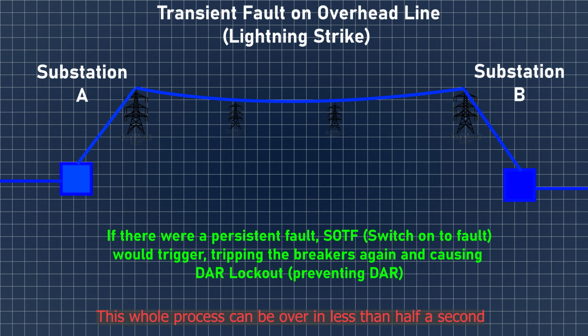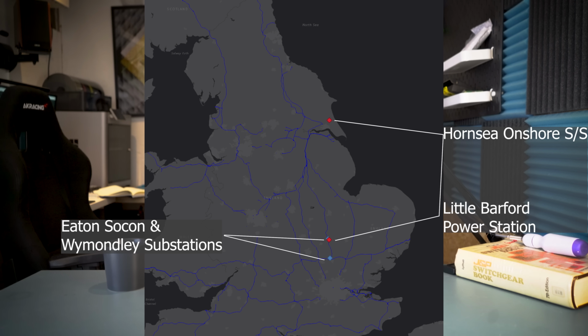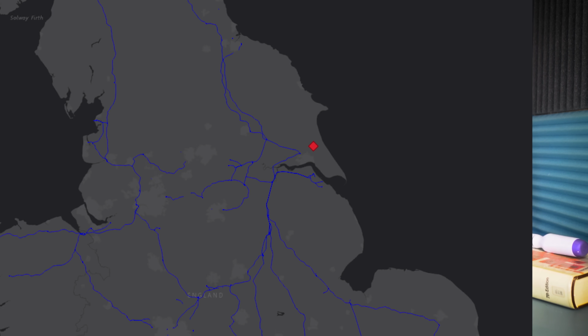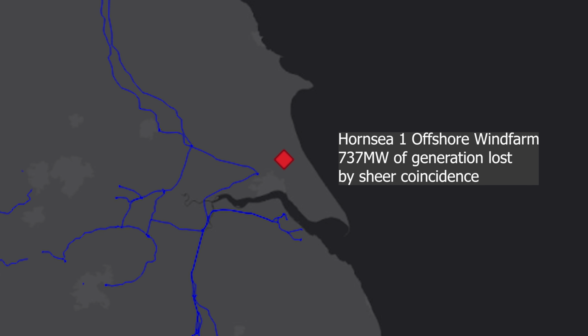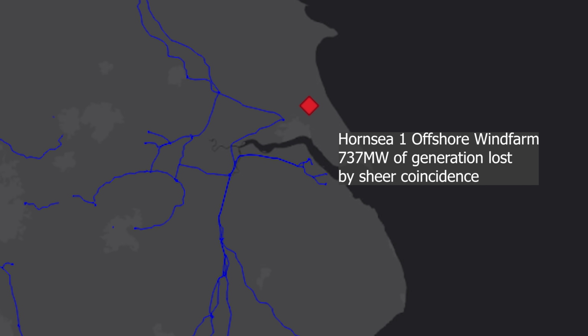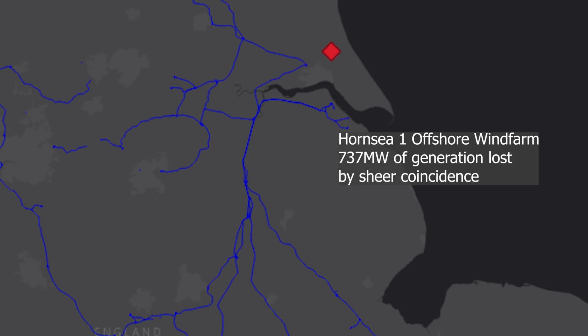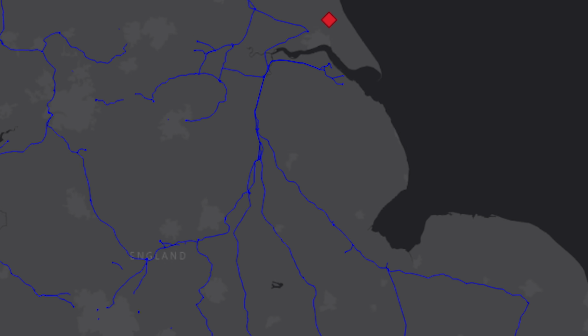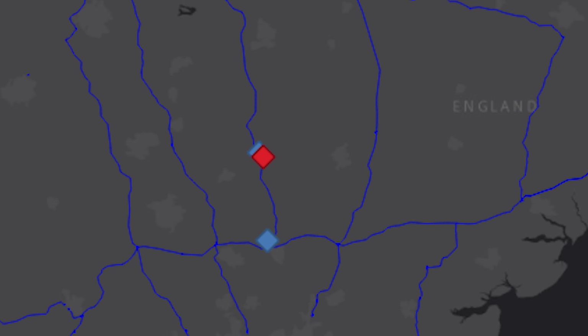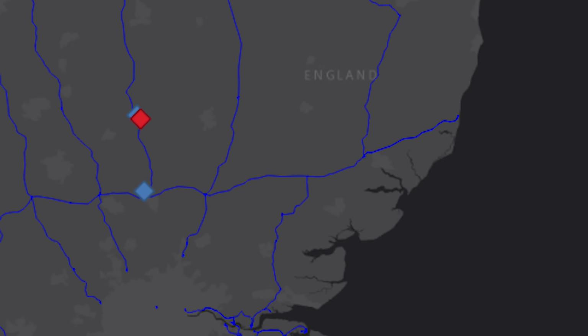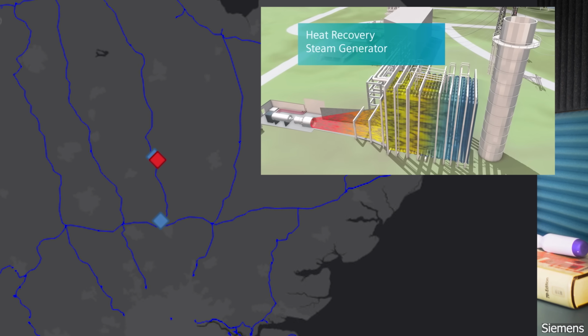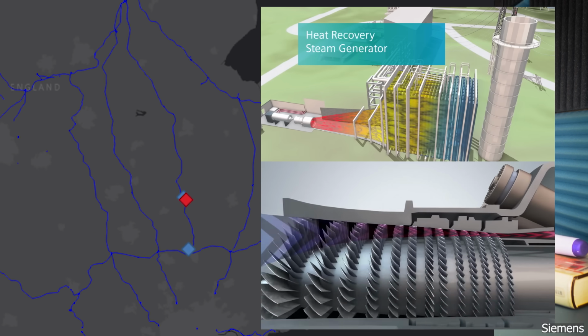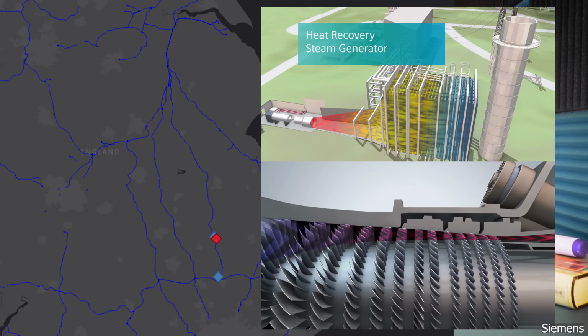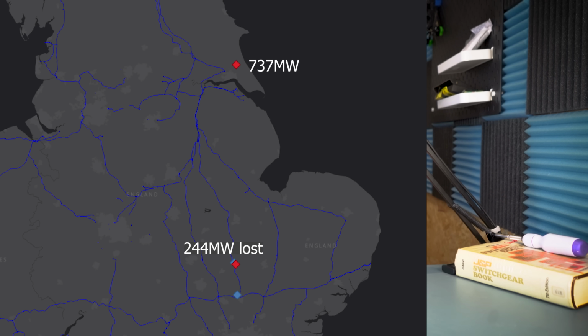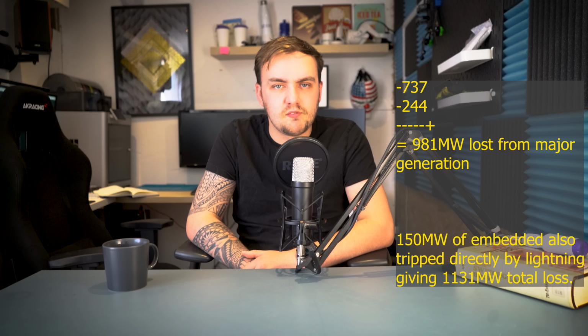At that same moment, vulnerabilities at two major generators were exposed. First, at the Hornsea 1 offshore wind farm, a technical control fault caused around 737 megawatts of wind generation to disconnect. Almost simultaneously, at Little Barford gas-fired power station, the steam turbine tripped offline, followed shortly by one of the site's gas turbines, removing another 244 megawatts. Altogether, almost 1 gigawatt of generation vanished in moments.